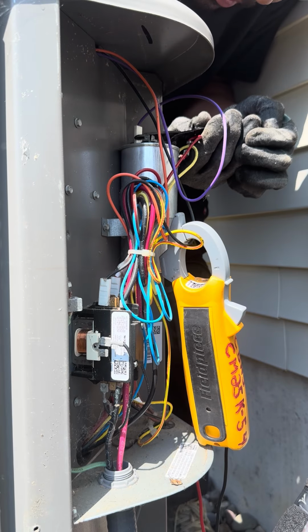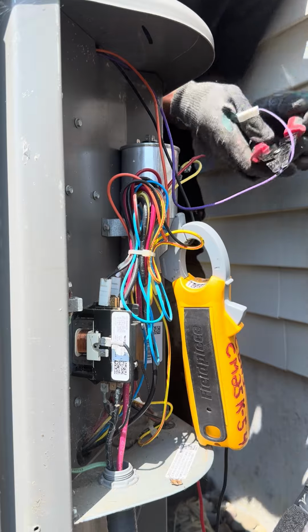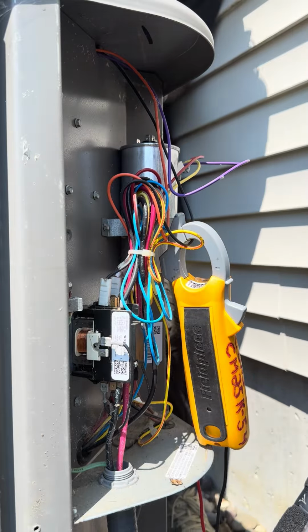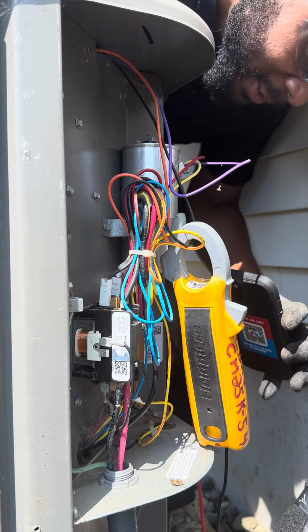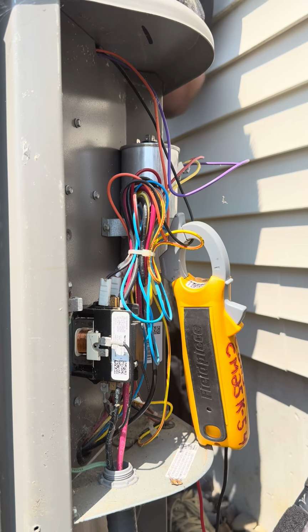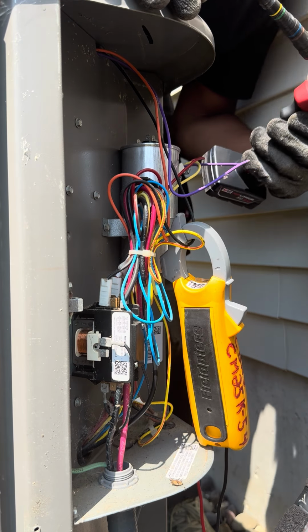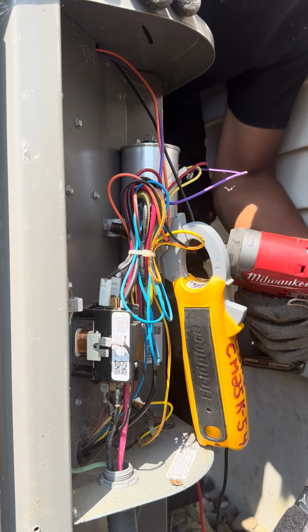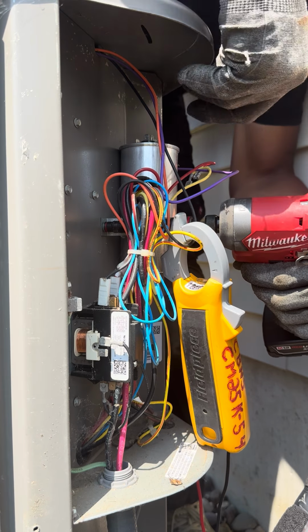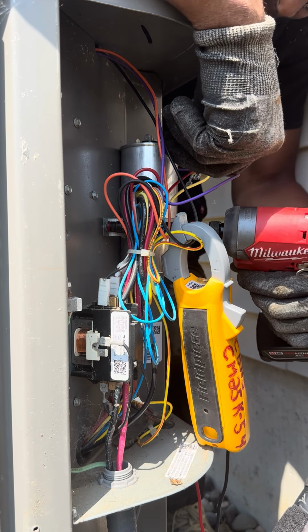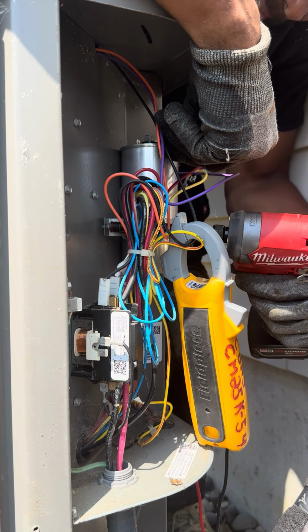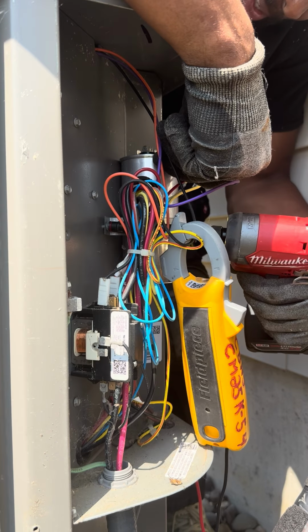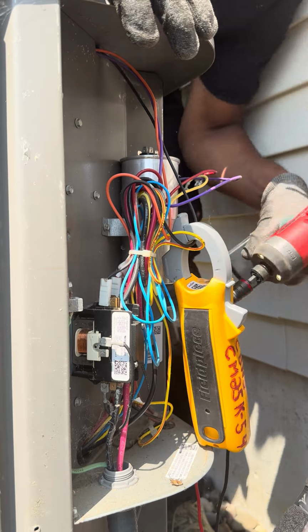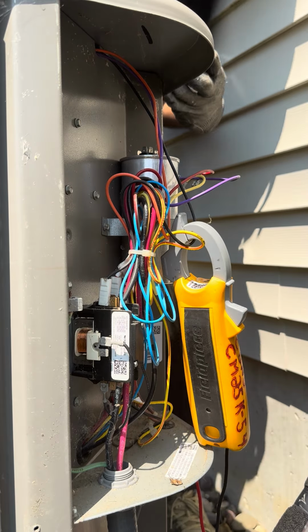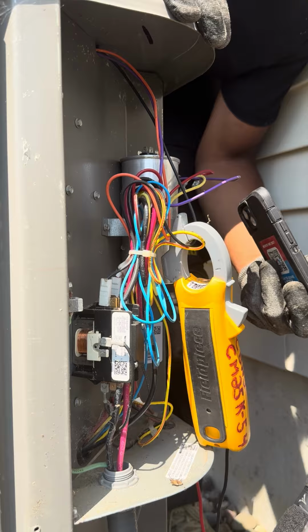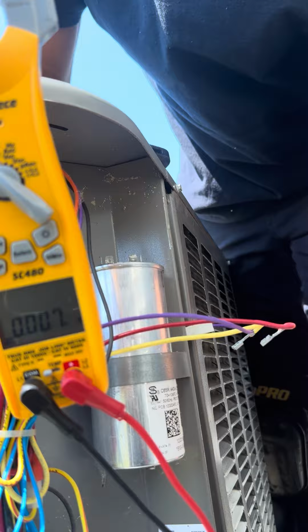Anytime you're doing a contactor and you want to check it, definitely turn the power off. Some people do it live - I've heard that some people have blown their multimeter doing it live, and it varies on everyone. To me, I like to turn it off, especially when people install capacitors where you can't see the rating of the microfarad, so I have to turn it around and figure out what the microfarad is for it.